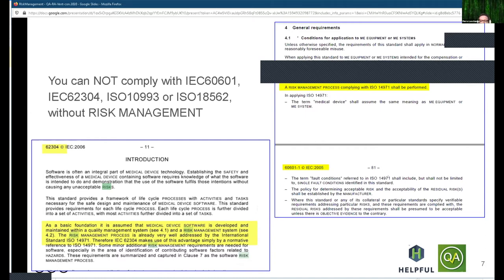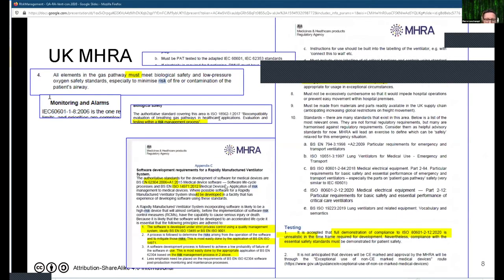If you look at the equivalent UK MHRA document, it's much more explicit. ISO 14971 is in there, and the concept of risk management is spread in many different parts of that document. So it's definitely something you can't avoid.